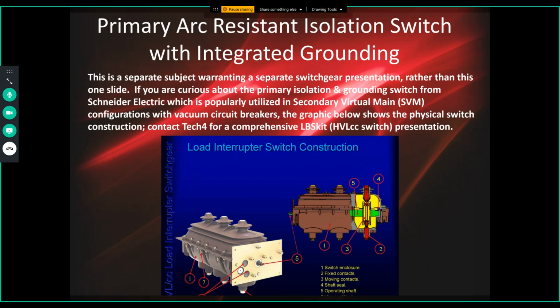And these last two slides, Mr. McClellan asked me to add to the presentation, not really directly associated with secondary virtual mains, but we have almost always applied this equipment in conjunction with a secondary virtual main architecture. And this is the isolation switch on the line side of the primary breaker. This is that Schneider Electric LBS kit switch. You can see the viewing windows here. So this is a cutaway view. There are two different viewing windows. One views the grounding switch or the grounding contacts, and one views the opening of the phase contacts.